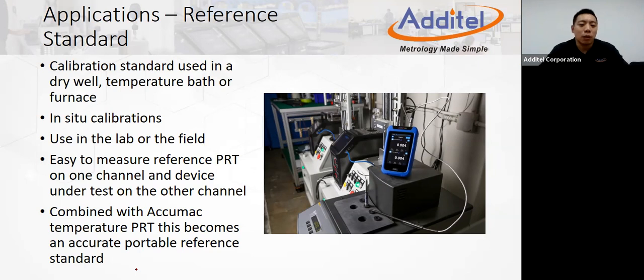Anyway, for the standard PRT connection, because we use a smart connection, you just need to plug in. For the very first time, you may need to input some coefficients about that probe. But for the second time, because we have the sensor library, you don't have to input it again. For the probe, we highly recommend AccuMac Pro because we have been cooperating for a long time, and a lot of customers already purchased the AccuMac probe. They have no complaint about it. Pretty reliable and pretty stable, pretty high accuracy. With the AccuMac Pro, even the first time using it, you don't have to input any coefficient because all the AccuMac Additel Smart Connection Probes already have the coefficients saved inside the smart connector. So you just need to plug into the 282 or 875 or 878, and then the device will recognize that probe automatically.